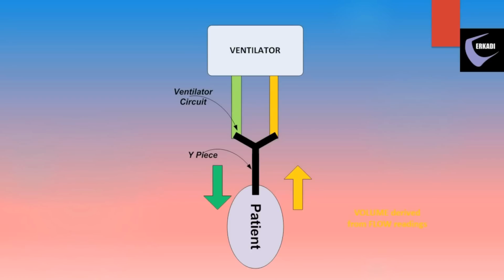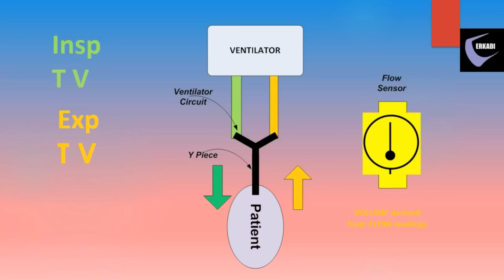This information is important, as said earlier, due to their being the biggest indicators for the clinician on the direction and respiratory effectiveness of therapy. This has given rise to the terminology inspiratory tidal volume and exhaled tidal volume. As we will see, different technologies have defined this differently. These measurements are arrived at using flow sensors. The differences in technology arise from the position in which the ventilators place them to measure flow and thereby volume.